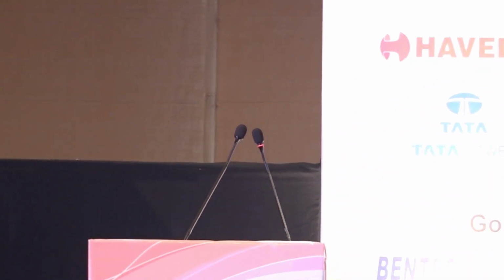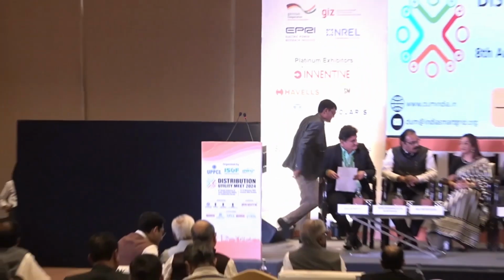Thank you very much. One key takeaway here is that if you put solar on every residence on a particular line, after the 10th or 11th installation the voltage will rise so high that it trips on 10% over-voltage. The solution is a smart inverter that adjusts VARs to manage the voltage and avoid this effect. We've seen this in many places: a normal unity power factor inverter will cause the 10th or 11th house to trip on over-voltage when there's less load.